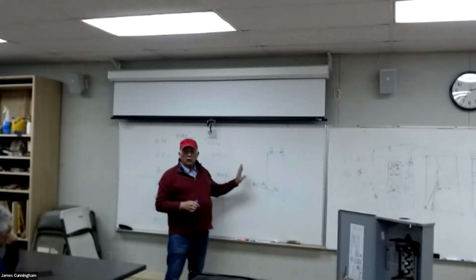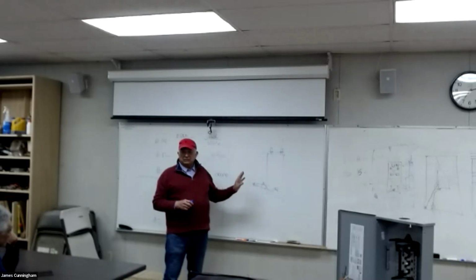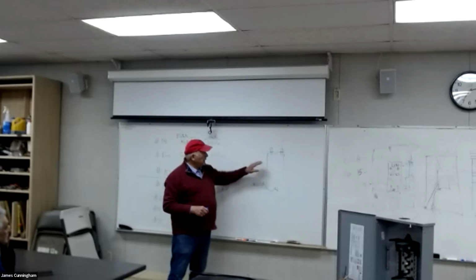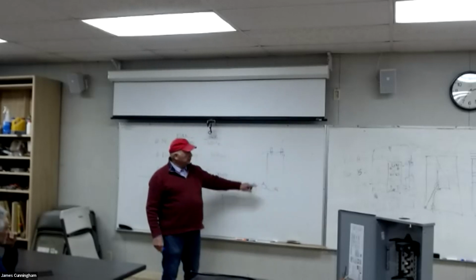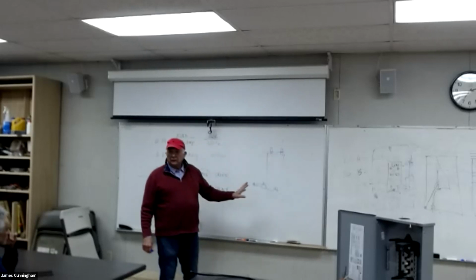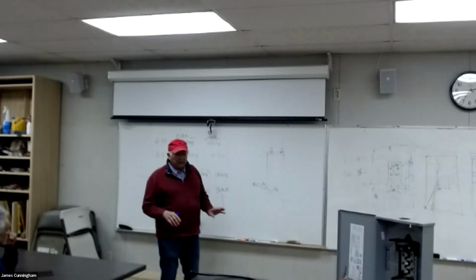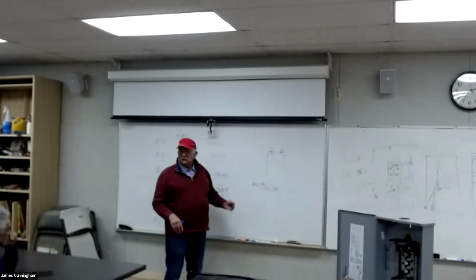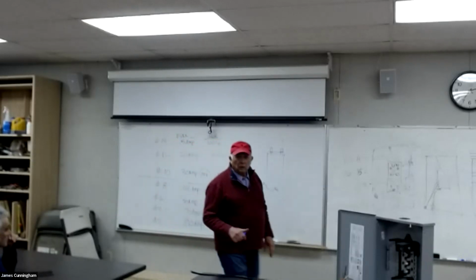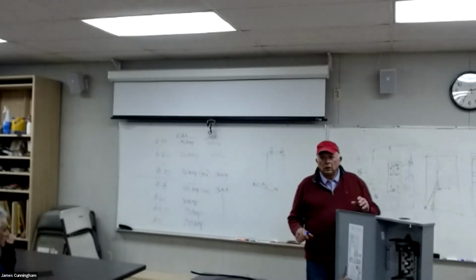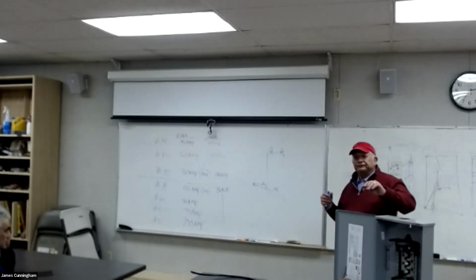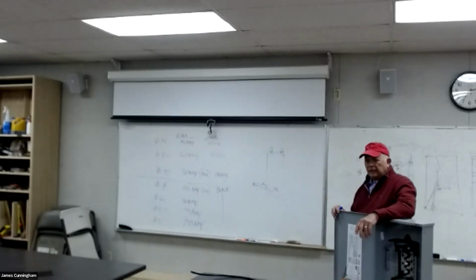So you have to do this grounding every time you do a service upgrade. And this doesn't go anywhere. It just connects these 3 together. It's not connected to the panel or anything. It's just these 3 connections right here, because the cold water is also connected to the ground somewhere else, on the outside. Right.